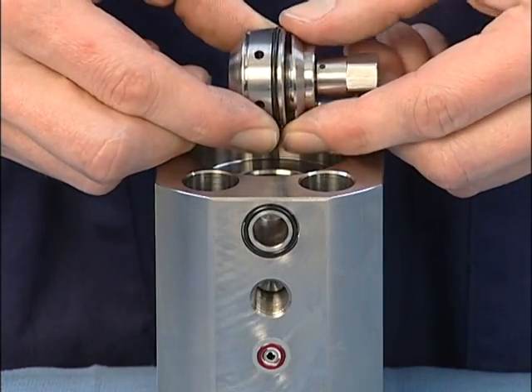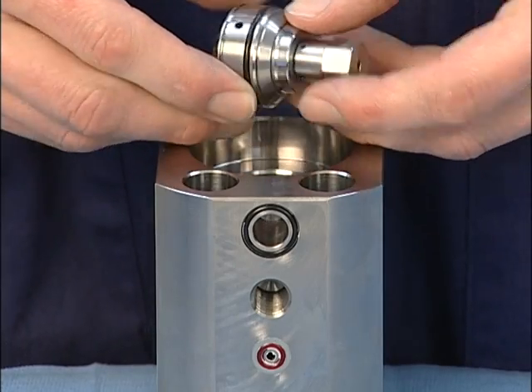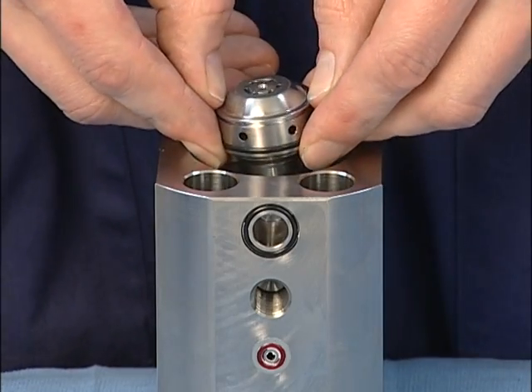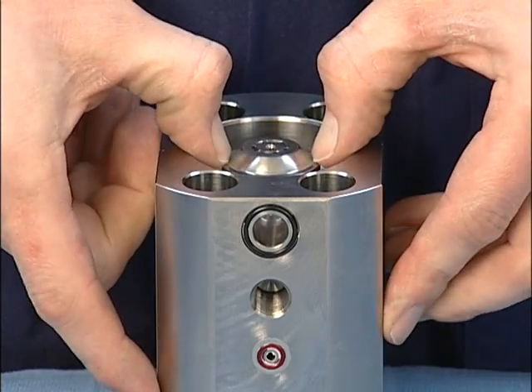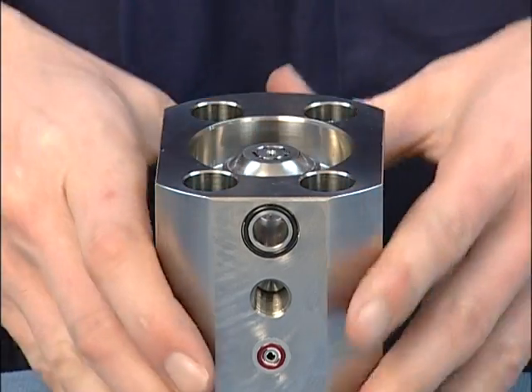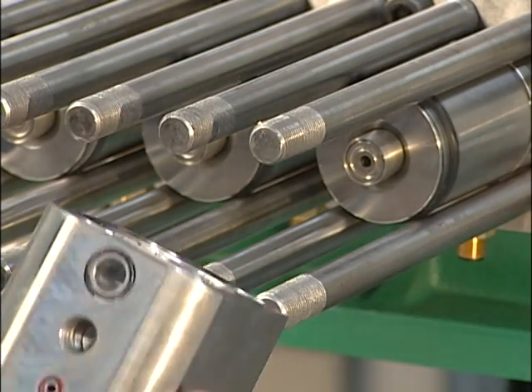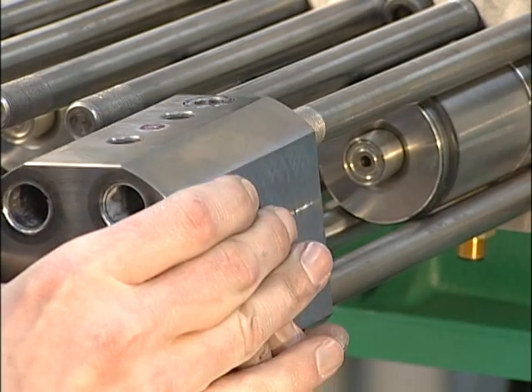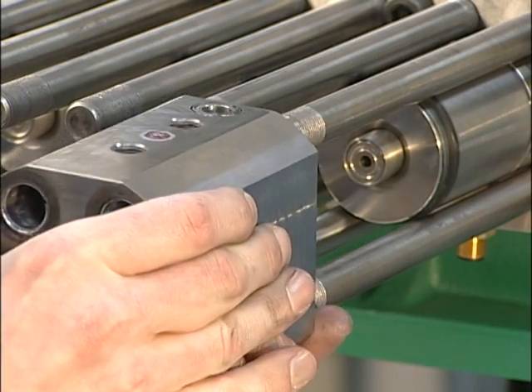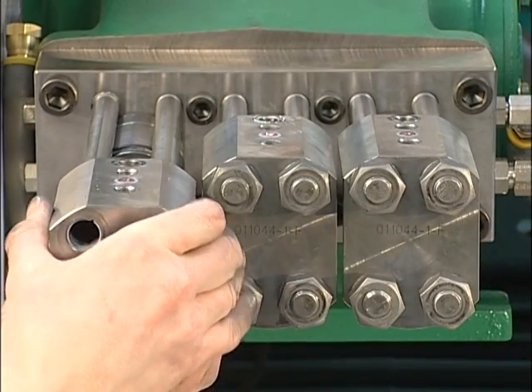If the static seal was removed, install the seal onto the outlet side of the check valve body and insert the check valve into the end cap. Install the inlet poppet and the check valve back into the pump using the minor repair service procedure. Return the pump to service following the startup instructions in the manual.